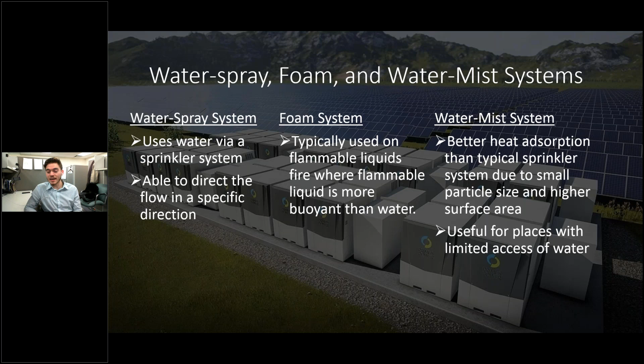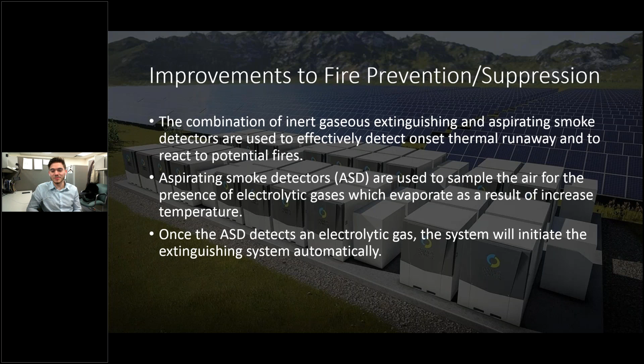So, improvements to fire prevention and suppression. The combination of inert gas extinguishing and aspirating smoke detectors is used to effectively detect the onset of thermal runaway and to react to potential fires. What an aspirating smoke detector does is sample the air for electrolytic vapors. If an electrolytic vapor or gas is present, it will initiate the extinguishing system automatically. This will avoid the thermal runaway, as simple as that.